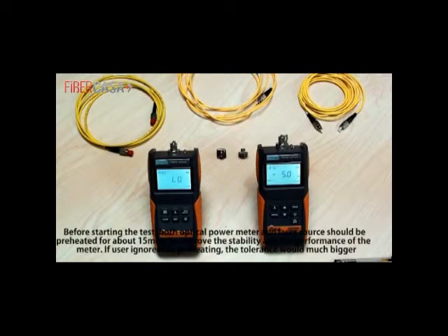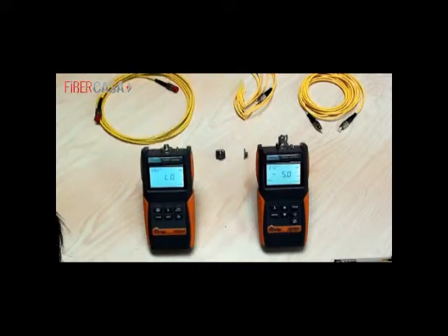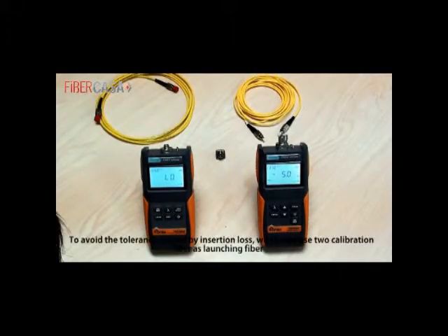Before starting the test, both optical power meter and laser source should be preheated for about 15 minutes to improve the stability and performance of the meter. If user ignores the preheating, the tolerance would be much bigger. To avoid the tolerance caused by insertion loss, we should use two calibration fibers as launching fiber.